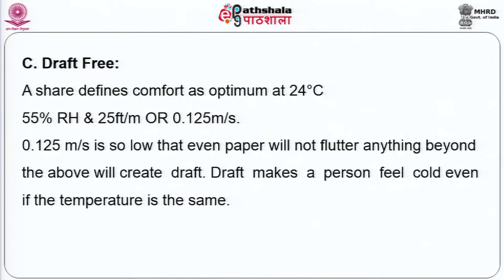Now, the last parameter that one has to worry about from the physical aspects of air conditioning is that the air conditioning should be draft free. Now, what is the normal draft that is allowed across a person in comfort air conditioning? It is basically 25 feet per minute or 0.125 meters per second that is permitted. Now, this is so small that even tracing paper on your table will not flutter at these velocities. Now, that is the kind of velocity that is expected in an auditorium, all over in all the seats.